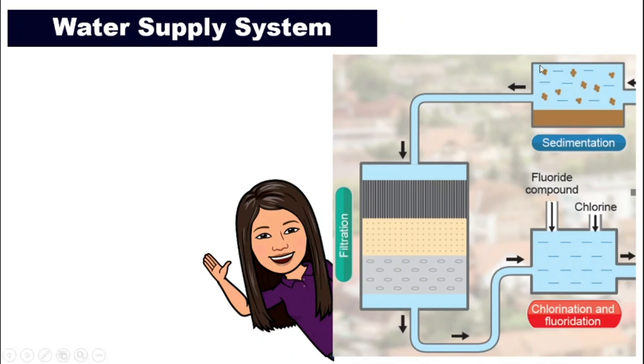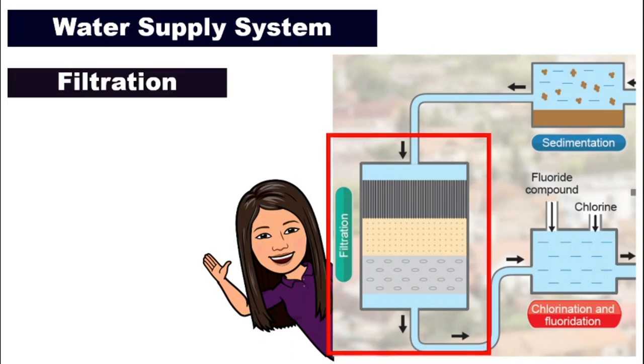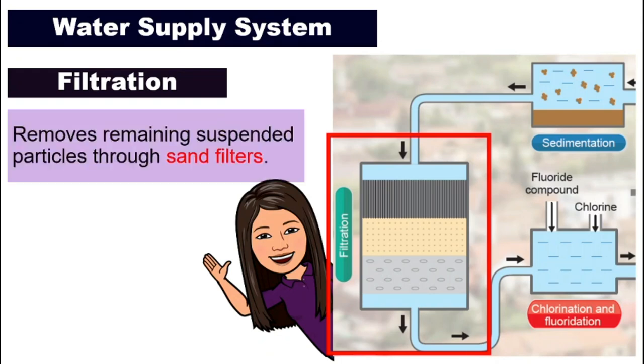The sedimentation and also the first filtration tank will not be able to get rid of everything. So the remaining suspended particles will be taken care of in the next tank, which is called the filtration tank. The remaining suspended particles, especially those very fine small ones, will run through the filtration tank which has sand filters — it is a giant sand filter — so the suspended particles can be filtered out. The water that comes out from here should then be clear and clean.